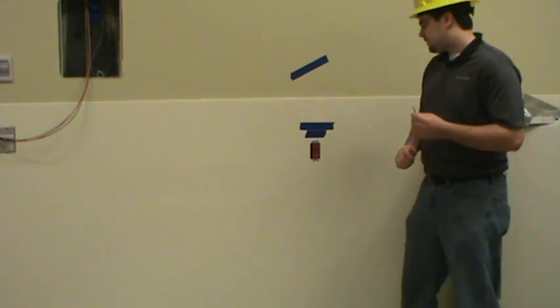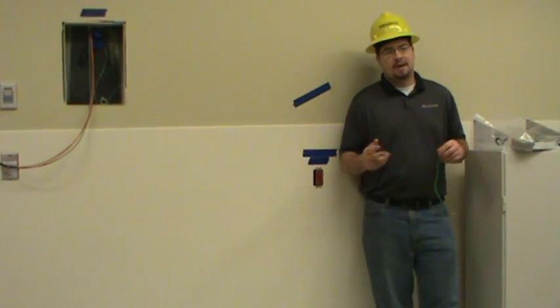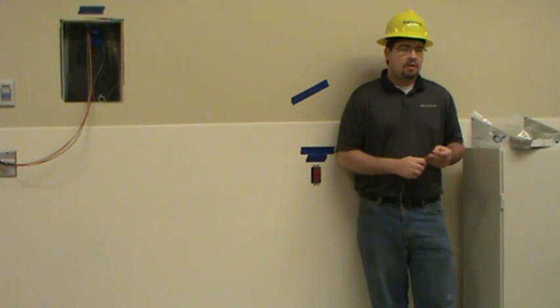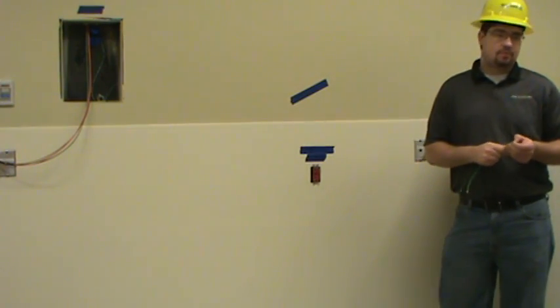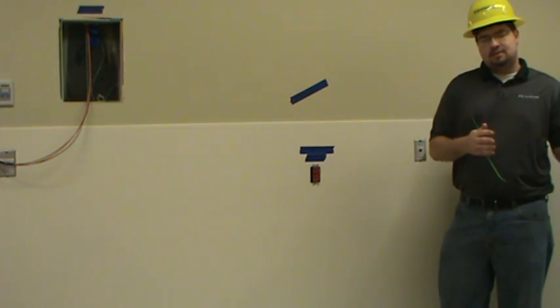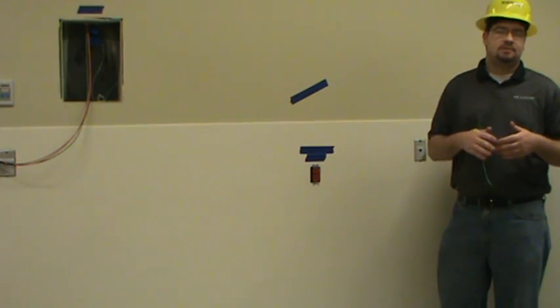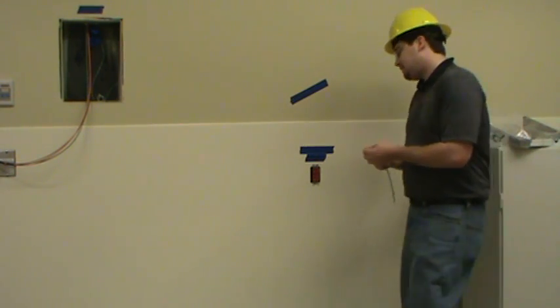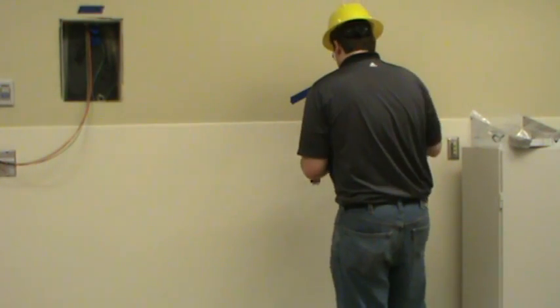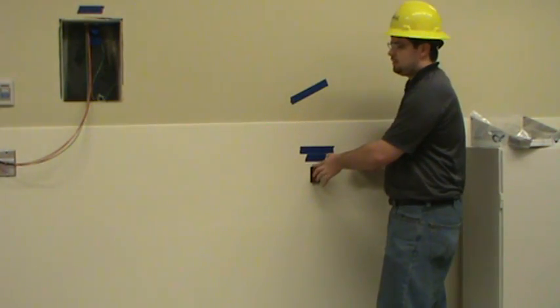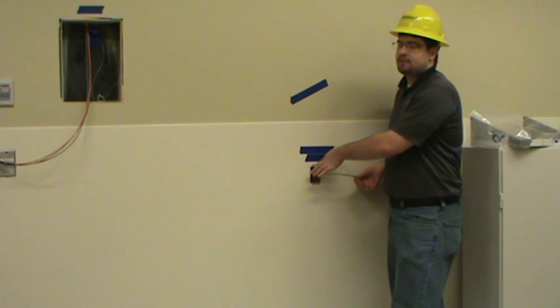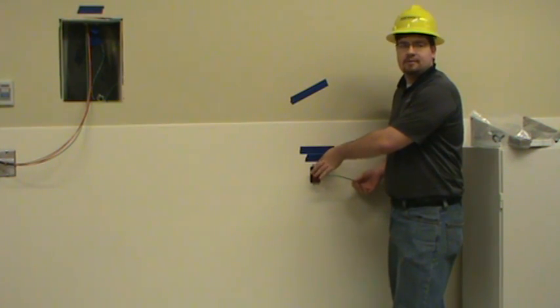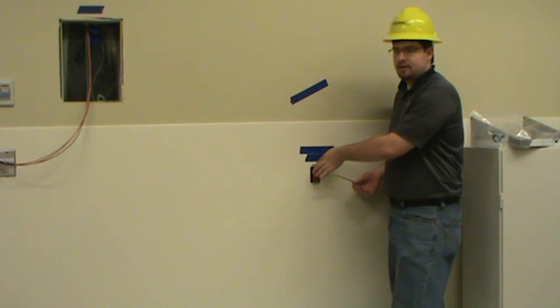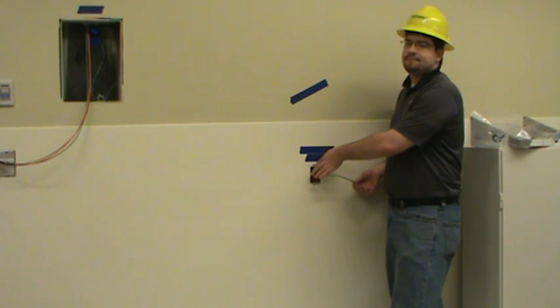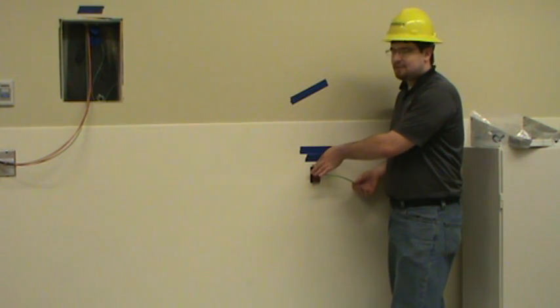So what our transformer is actually doing, it has that high impedance back to ground, isolated from ground. So if anything were to get shorted through ground, that impedance is going to add in series to whatever is being shorted. So we take that high impedance, add it to my low impedance, and I'm technically getting electrocuted now, but with whatever the monitor is reading. So let me take a look. 2.9? 2.9. So I got 2.9 milliamps going through me. I can't really feel anything, not even a tingle.